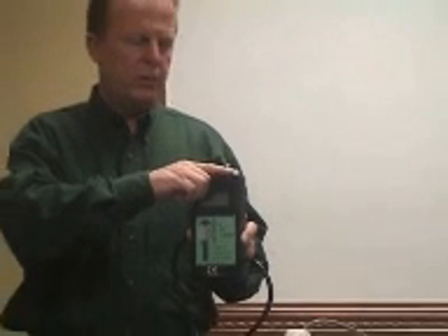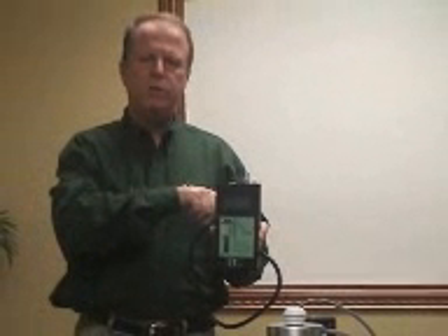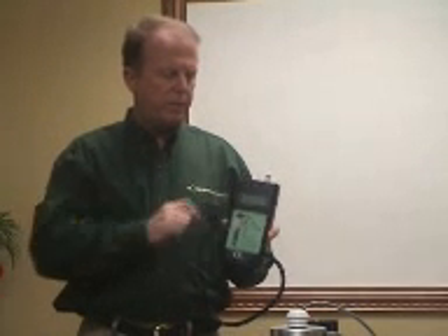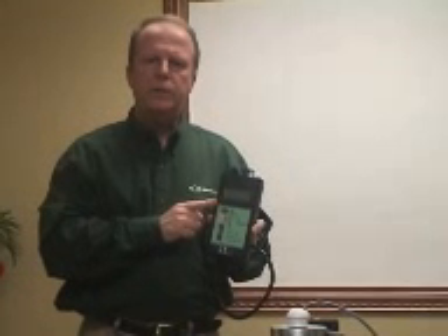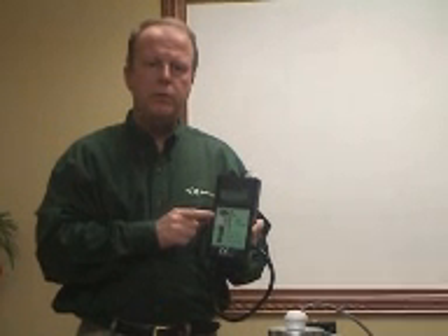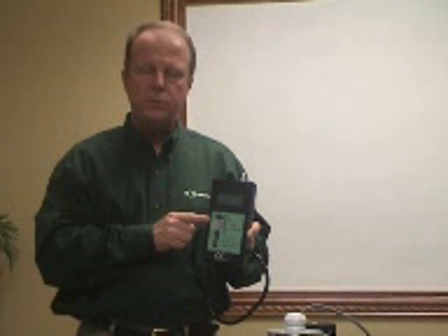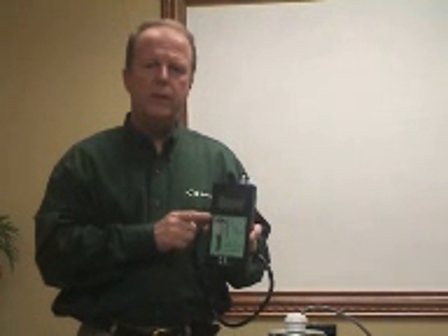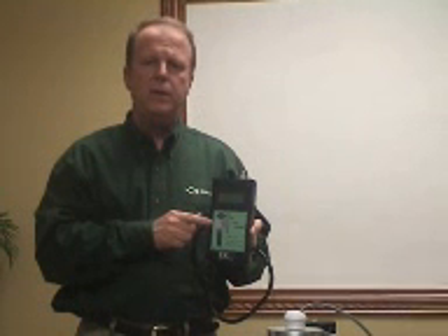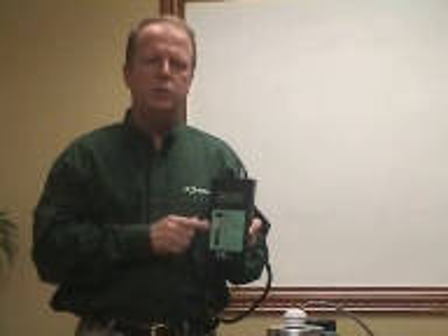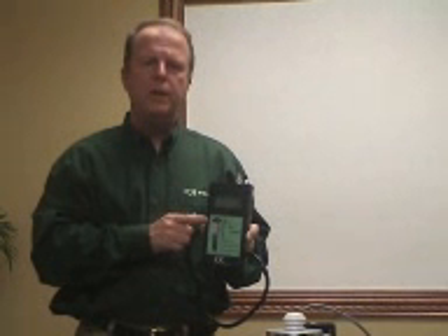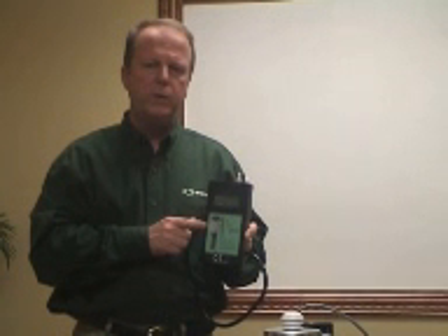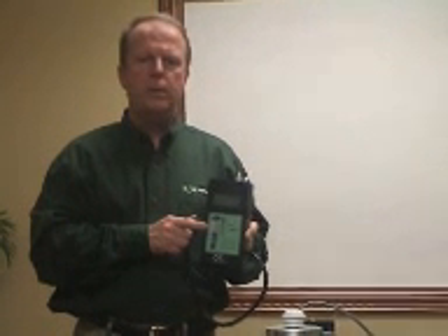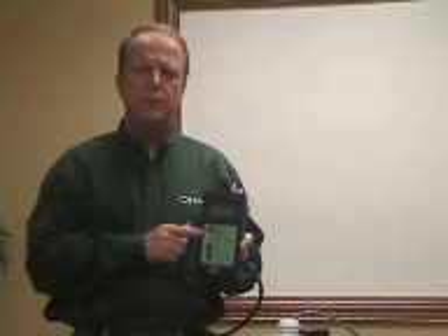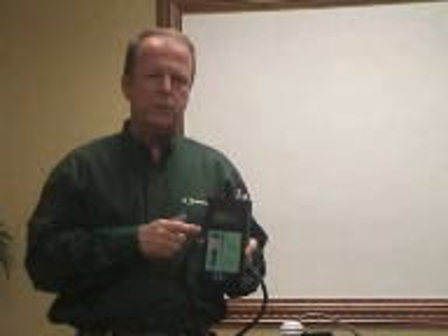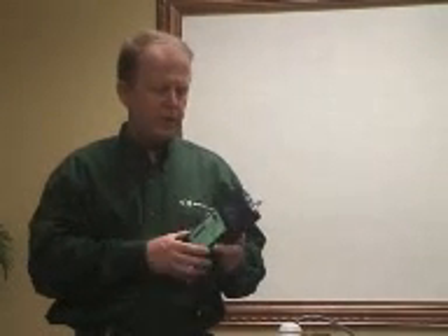It has an ambient temperature sensor and a barometric pressure sensor, and the unique thing about the unit is that it not only provides you the data in Q actual, which are volumetric conditions, it also gives you Q standard, which can either be at US EPA conditions, where it converts the flow rates to 25 degrees C and 760 millimeters of mercury, or we have what we call our European model, which is at 0 degrees C and 1 atmosphere. So we make a lot of different models for different applications.